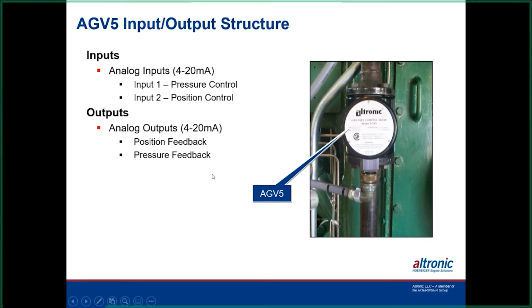This output here is what it's talking about. There's a pin that runs up inside the board and moves up and down in it, and that board has a coil around it. If that clearance gets out of whack, it gives you a false reading on the output. So please, unless you know how to calibrate one, don't get in there and move that board around if you plan on using that part of the feature.